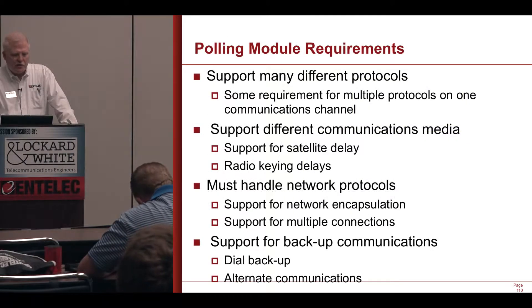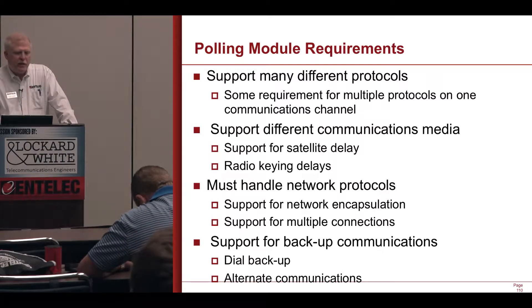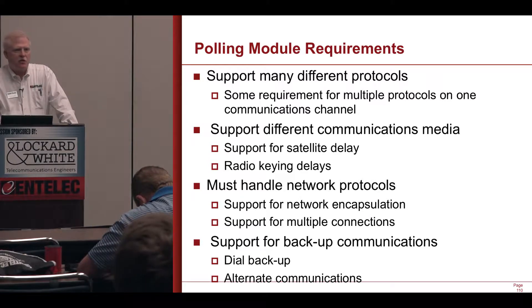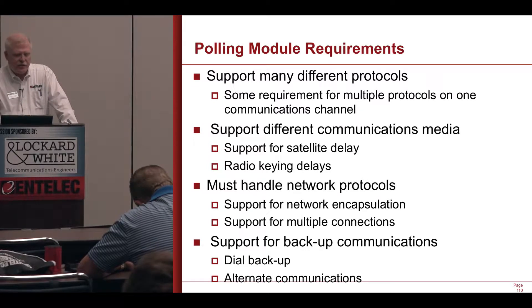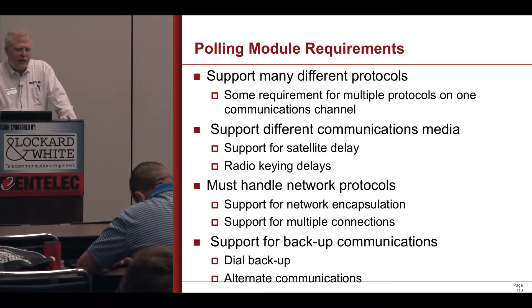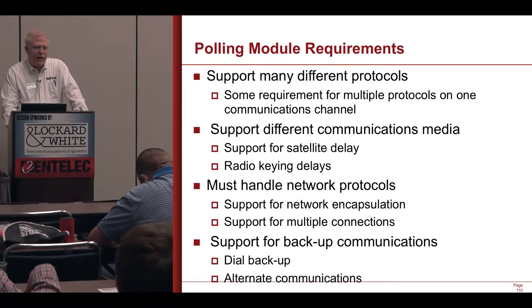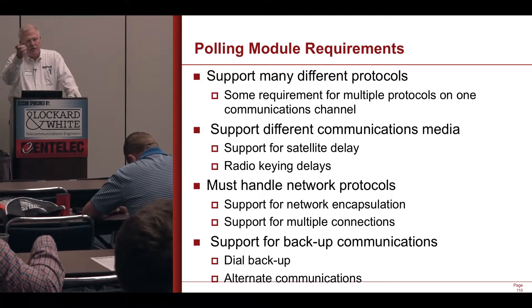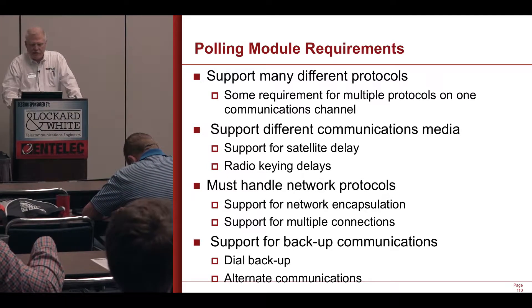The polling module is one of the most critical pieces of the system. It needs to be able to handle multiple protocols, it's got to support multiple media, and it needs to support a primary polling path and secondary polling path if the primary path fails. It's got to handle network protocols and encapsulation — for example, taking Modbus and putting it inside of TCP — and it's got to support backup.